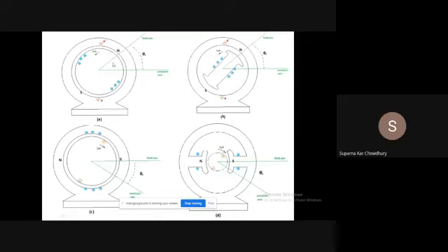But on the other hand, if we go for the cylindrical rotor construction, it is a smooth structure, so when it is rotating at a high speed, the windage loss and the noise will be less compared to the salient pole structure. So for turbo alternators used with thermal power plants, we will go for cylindrical rotor construction. This cylindrical rotor construction typically has 2 or 4 poles, maybe a maximum of 6, not more than that.